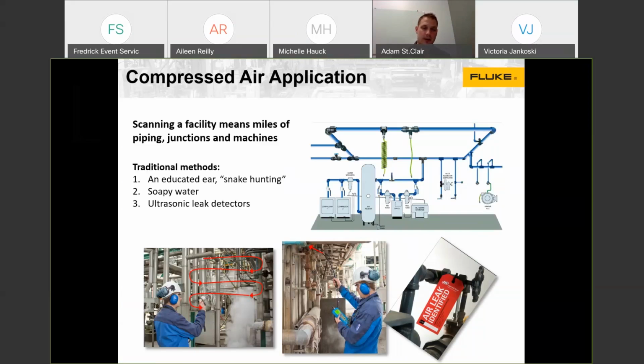The other thing our customers were telling us they did was use soapy water. They would take a squirt bottle, fill it up with soap and water, and go out and squirt all of the different components, fittings, connection points, flanges, gaskets, valves, and all the different areas where there could be leaks. When they needed to find one, they'd just spray with soapy water and hunt for any spot that spit bubbles back at them.